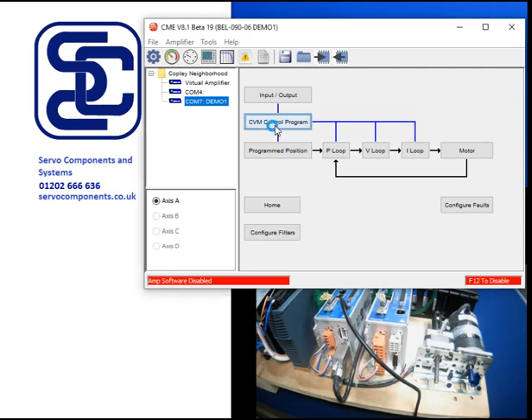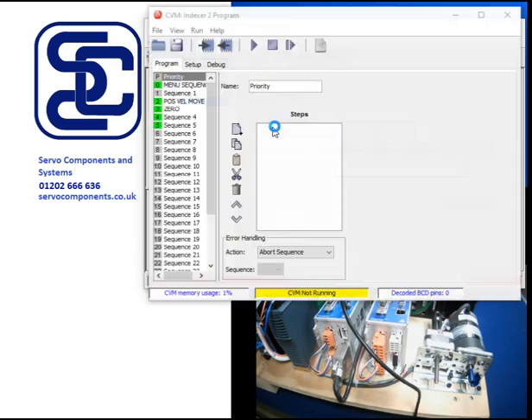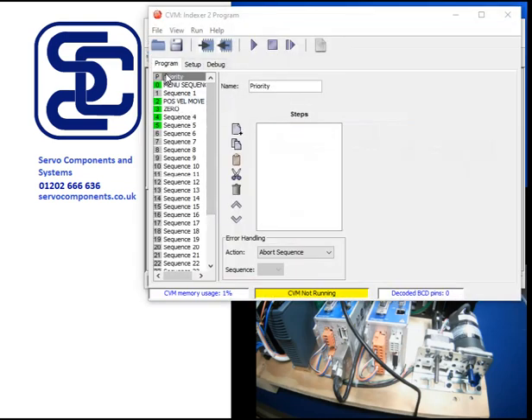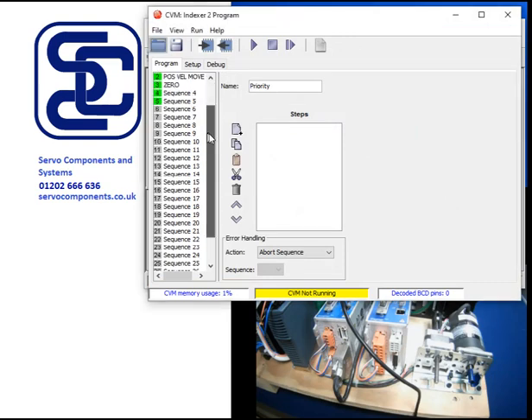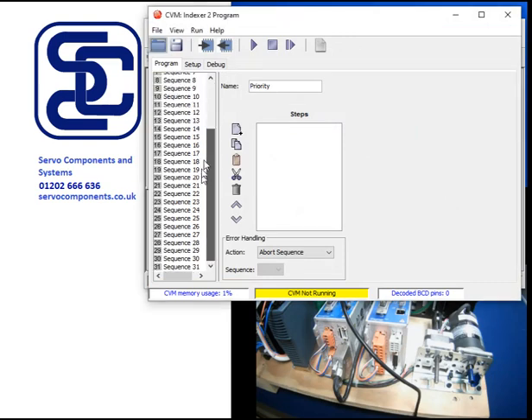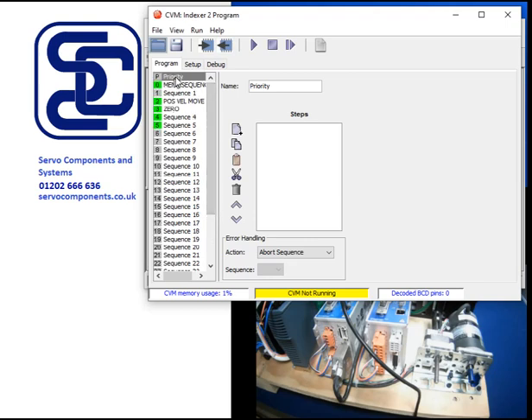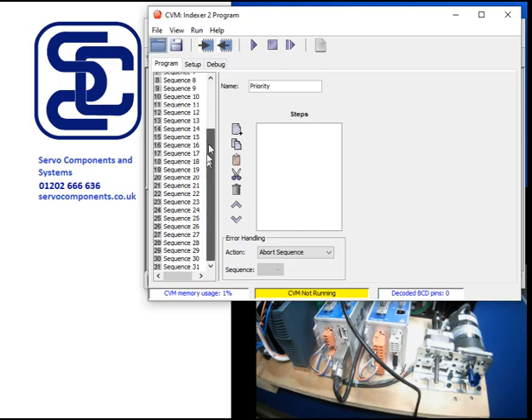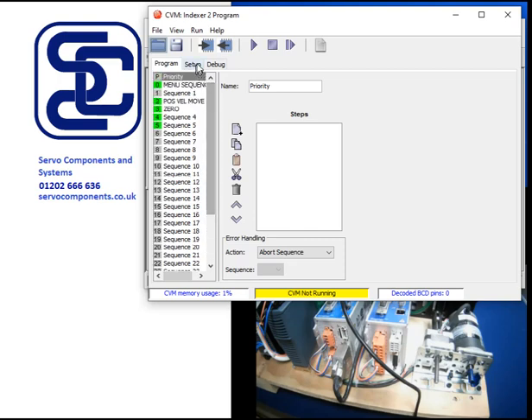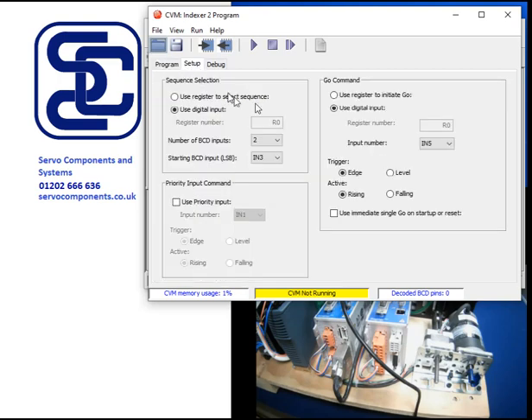But you can turn the whole drive into a simple PLC driven application using the CVM control program. If I click on that, we'll see that we've got a number of control programs down the side here. I can have up to 32 plus a priority program which is activated on its own dedicated input. The actual 32 programs are selected using a sequence selection which we'll go into on another video.